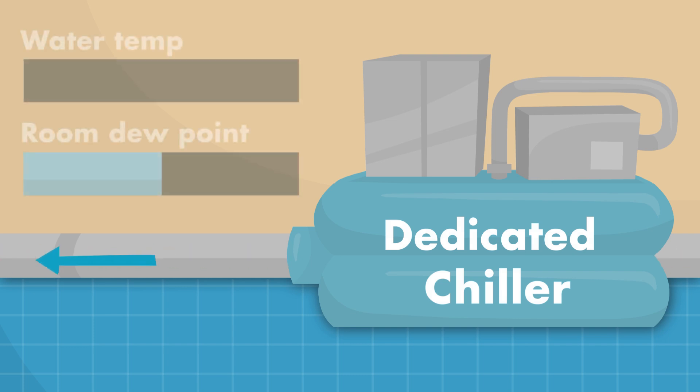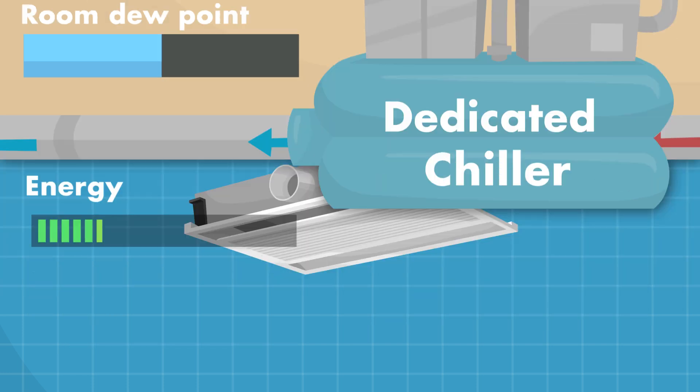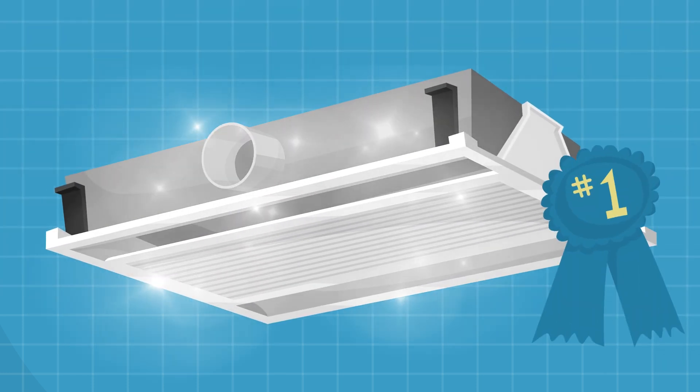Meanwhile, to effectively cool a space, the water circulating through the coil need only be chilled to a temperature just above the room dew point. That means the dedicated chiller uses less energy to deliver the same cooling. When you add up all these savings, it's easy to see why active beams are so efficient.